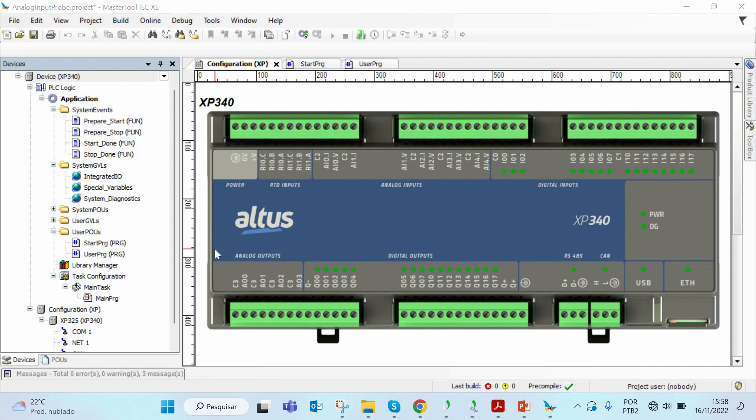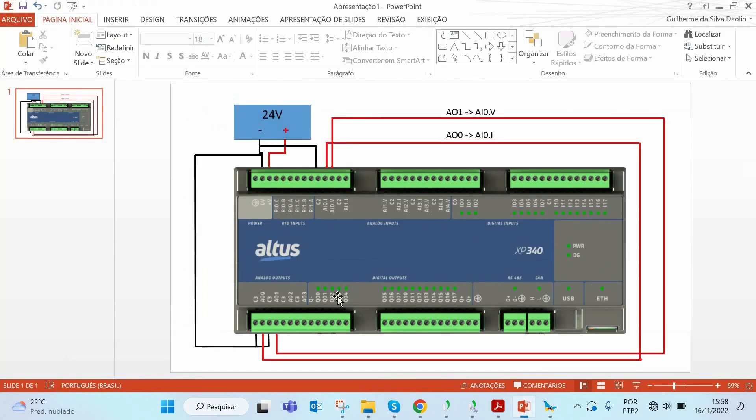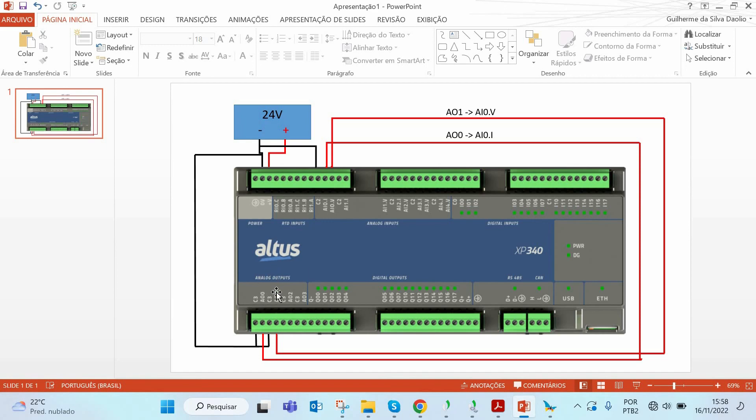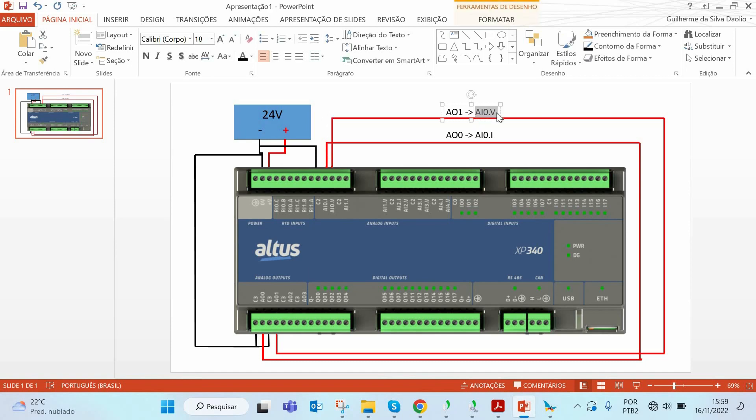For this example we will be using our analog outputs as our signal generators, so our analog outputs will be directly connected to our analog inputs as shown in this image. I have my first analog output AO0 connected to my AI0.i so this will be my current generator and my second analog output AO1 is connected directly to my AI0.v. I'm using my AI0 for both my analog inputs but one is for voltage and one is for current.